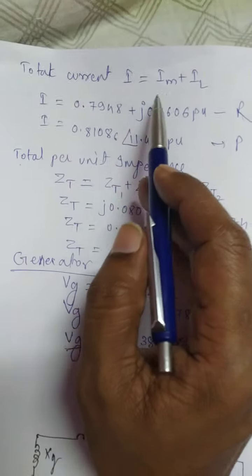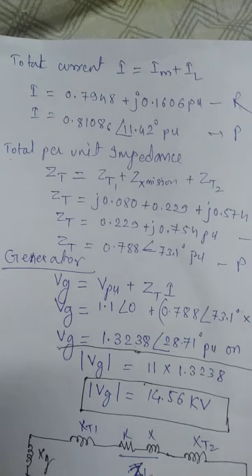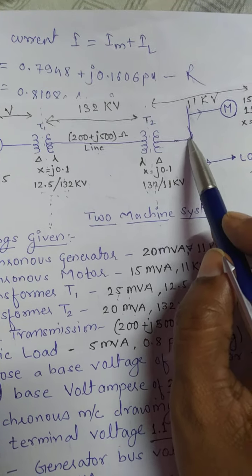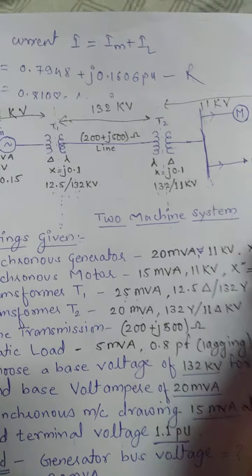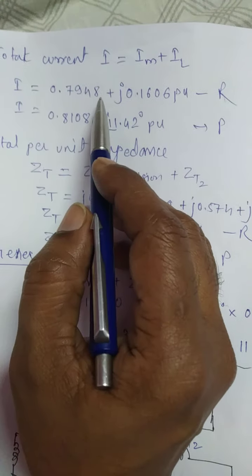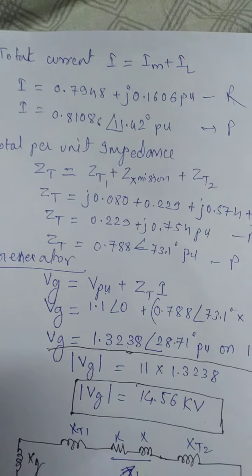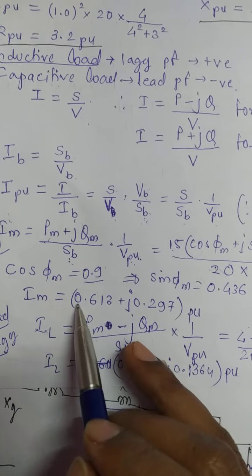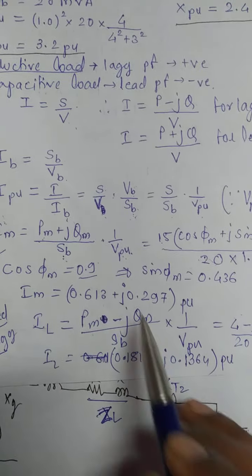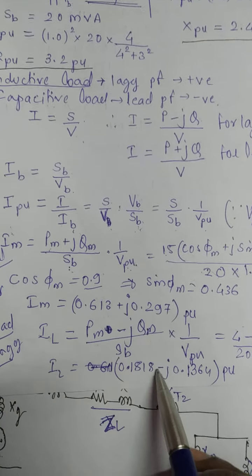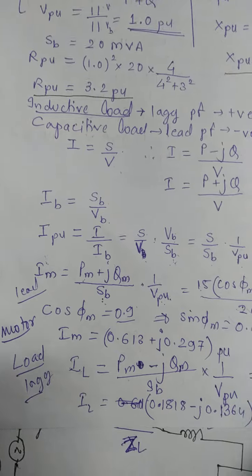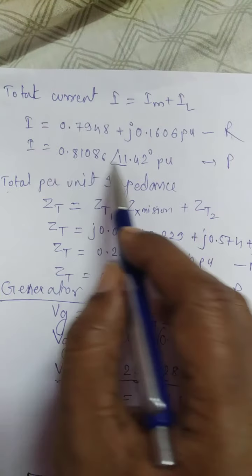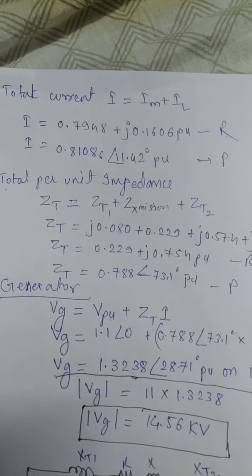The total current I equals IM plus IL. In this diagram there is a transformer, and the total current is divided into the motor and load at 11 kV. Therefore the total current will be 0.7948 plus IM, which you already calculated as 0.613 plus j0.297. Adding this load current and motor current gives the total current. This is the rectangular value of the total current and this is the polar value.